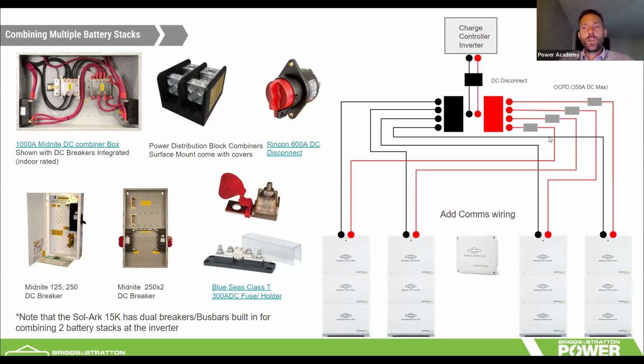The combiner also should have overcurrent protection built into it. If you've got multiple stacks, you'll want to have overcurrent protection built in. That could be a fuse or a breaker, and the controller itself already has digital overcurrent protection built in. For the different options here, I'm showing a Midnight 1000 amp combiner up here in the top left. This is a very common one. You'll see some breakers here on the sides. I think you can do up to 8 of these breakers, maybe it's 10 breakers, on a single Midnight 1000 amp combiner.